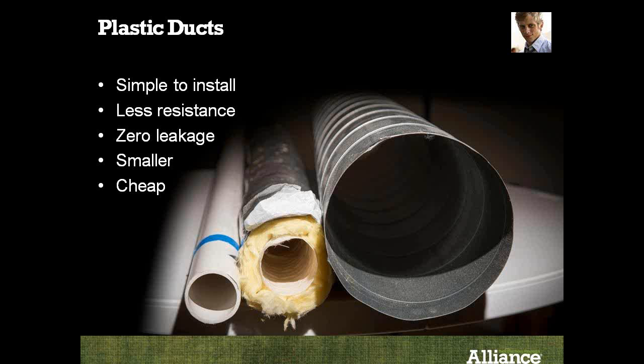So these duct systems are smaller, and we've talked about some of those advantages. It's easier to bring that ductwork into conditioned space. It can run through, for example, interior partition walls much more easily. And if you have to run, say, a bulkhead for some of this ductwork, you're not sacrificing a whole foot or 16 inches of your ceiling for that bulkhead. You might only sacrifice 4 to 8 inches. So it's much easier to bring this ductwork into conditioned space.